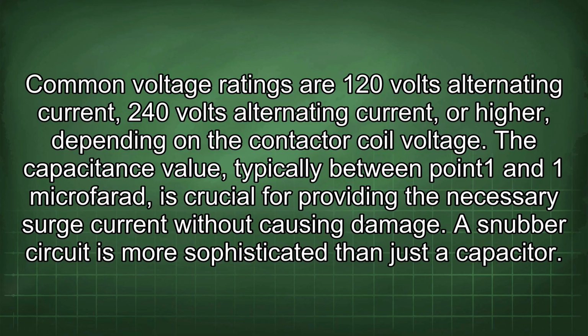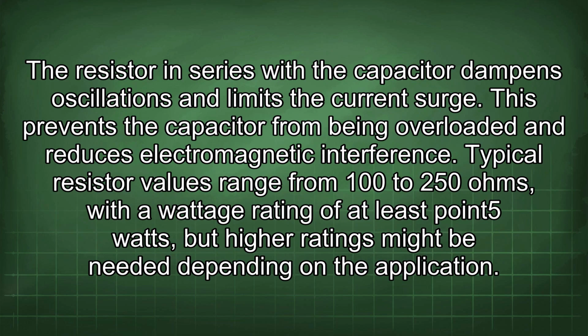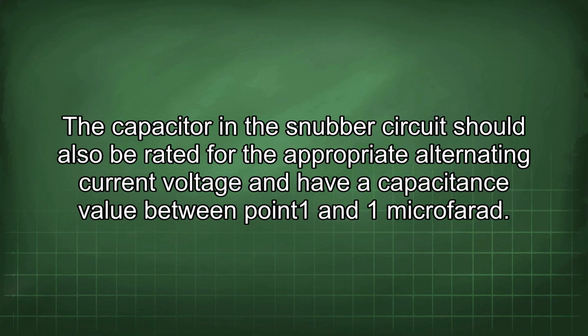A snubber circuit is more sophisticated than just a capacitor. The resistor in series with the capacitor dampens oscillations and limits the current surge. This prevents the capacitor from being overloaded and reduces electromagnetic interference. Typical resistor values range from 100 to 250 ohms, with a wattage rating of at least 0.5 watts, but higher ratings might be needed depending on the application. The capacitor in the snubber circuit should also be rated for the appropriate alternating current voltage and have a capacitance value between 0.1 and 1 microfarad.